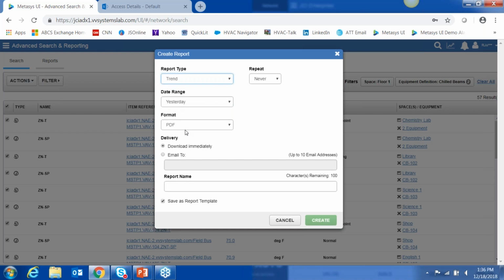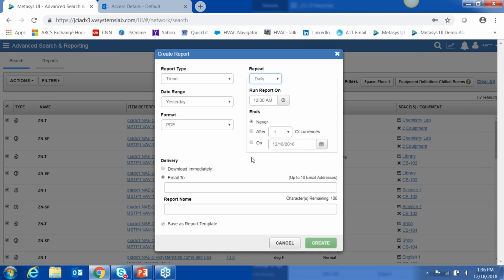Let's select a trend report, and I can immediately download that report. What's new at Metasys Release 10 is the ability to schedule these reports to automatically occur on a regular repeating cadence. I've got the choice of every day, every week, every month, or every year, so operators can set up reports on the points I've selected for a certain period of time and have them downloaded or emailed to an email distribution list. Then I can name the report, this will be my daily trend report for floor 1, and create that scheduled report.